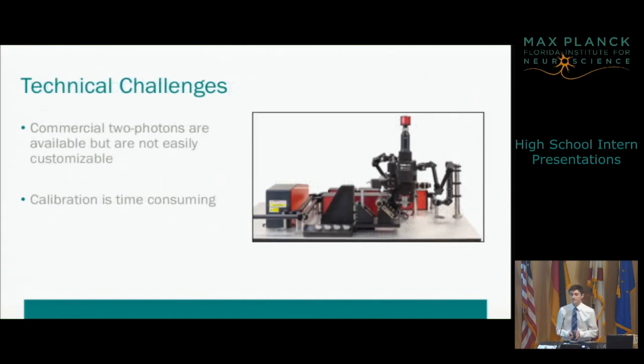However, they do face technical challenges when using the 2-photon microscope in non-conventional uses. They are available, but not easily customizable. So for our purposes of using it from an off-angle perspective of the brain, it is harder to use. Calibration can also be time-consuming, as every time you move the 2-photon microscope, it needs to be recalibrated, including the laser strength and the angle.